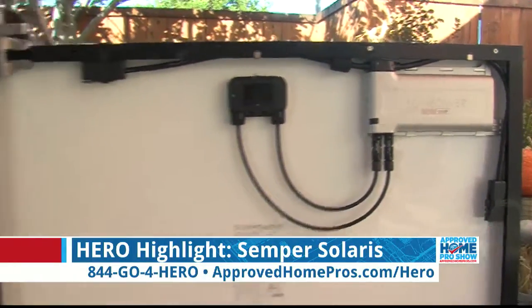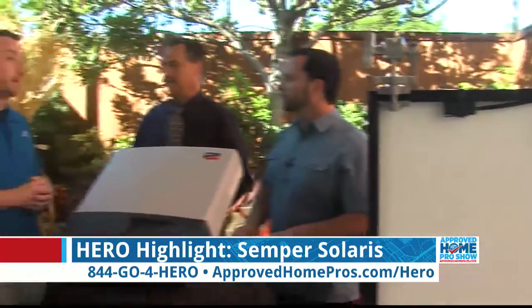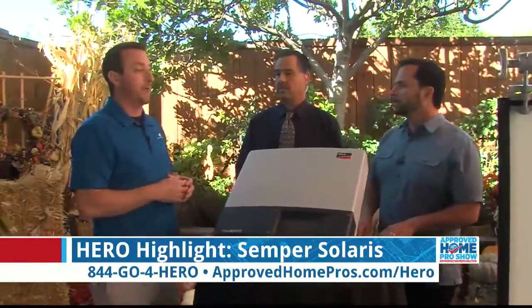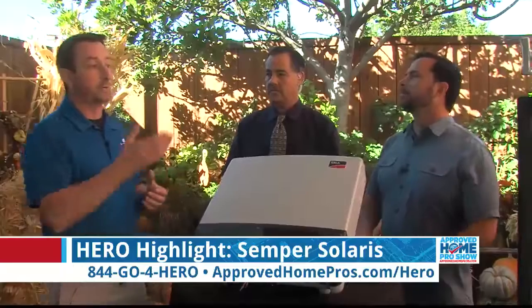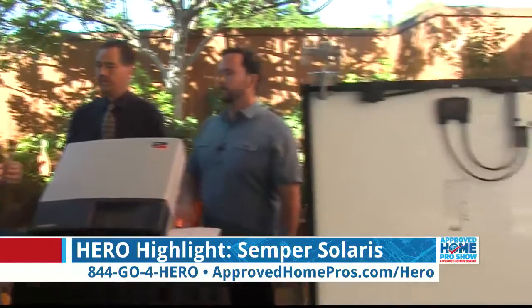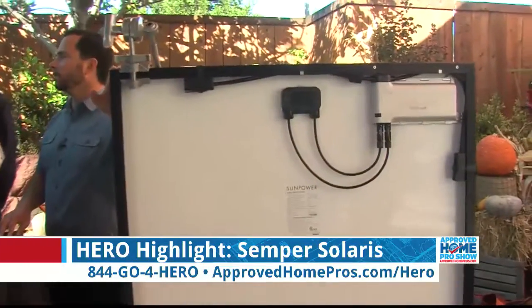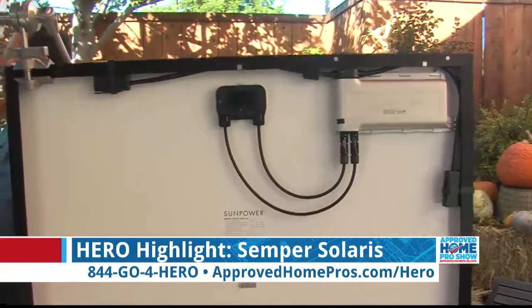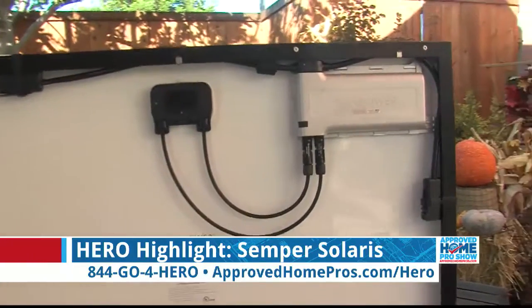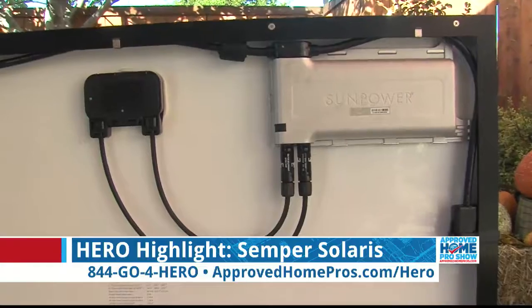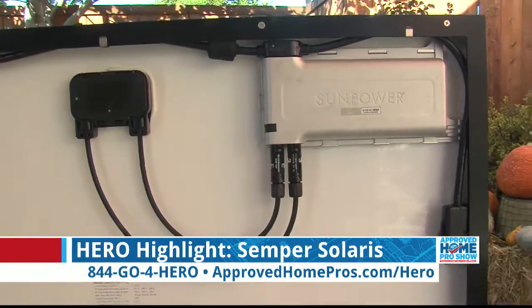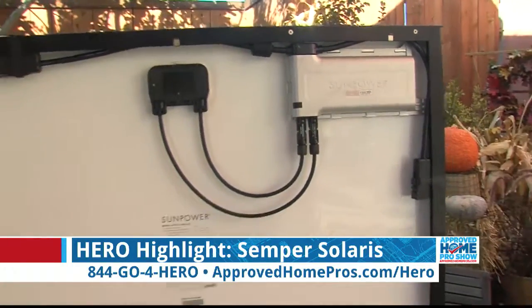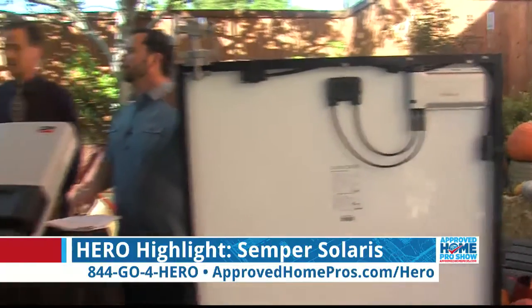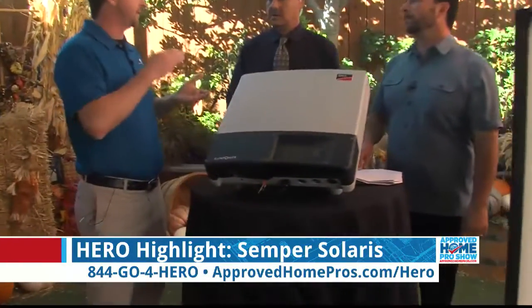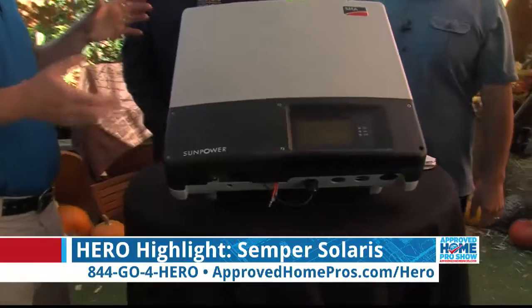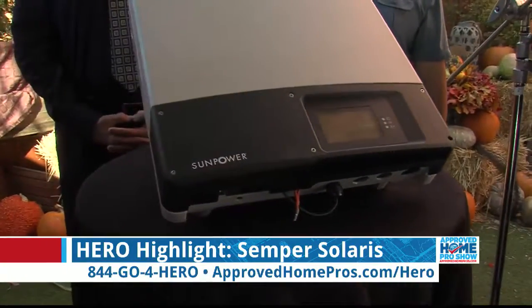So, Robert, what are the advantages of one over the other? Well, it really depends on the home and what you're trying to achieve. What's really nice about the AC PV is that they work really, really well when you have shading issues, you have roofs where there's lots of different tilts and angles and azimuths, and you have panels at different directions. With string inverters, what works really well is if you have all the panels on one roof at the same pitch and same azimuth. A string inverter works really, really well because you don't have those other issues to contend with.